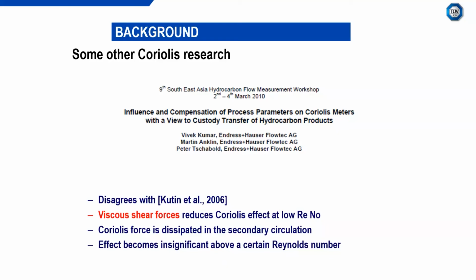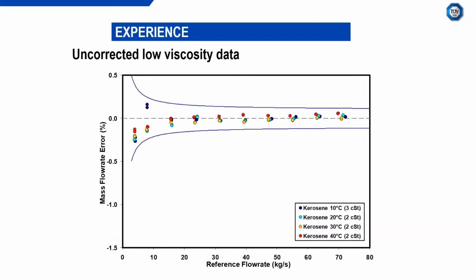They then apply a linear correction for Reynolds number, basically for the effect that these Reynolds numbers have on the mass flow output. I'll show you some data to show you what that roughly looks like. This was some of the work we completed back in 2008 that I mentioned earlier when I first joined NEL. We had a low viscosity fluid, kerosene, calibrated at 4 temperatures: 10, 20, 30 and 40 degrees Celsius. Because it's a low viscosity fluid, temperature doesn't really affect the viscosity too much, approximately 2 to 3 centistokes.